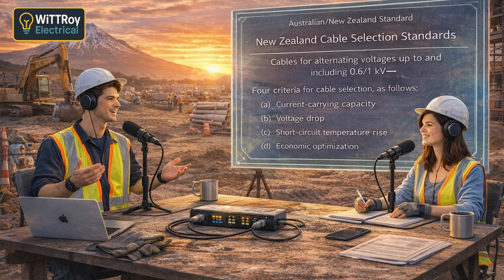This is the exam part. First, find the current. Same as before. Second, find the cable length. From supply to load? Third, get the millivolts per amp per meter value. From the table. Then multiply. Voltage drop equals millivolts per amp per meter times current times length. So it's actually quite simple. Yes, once you see it that way. And then compare with the allowed limit.